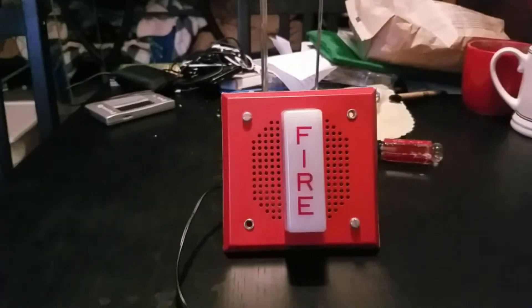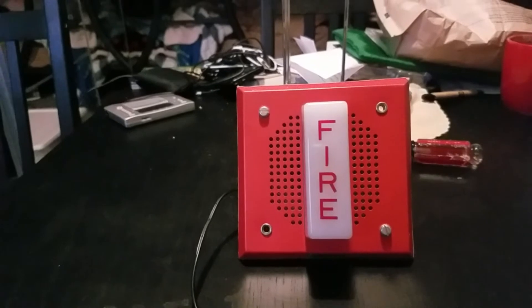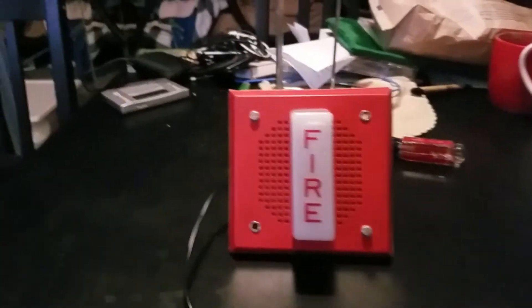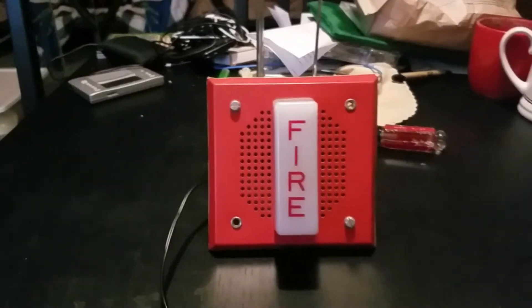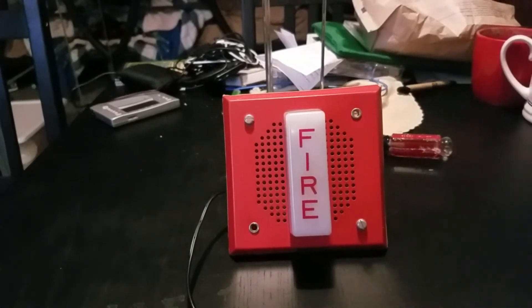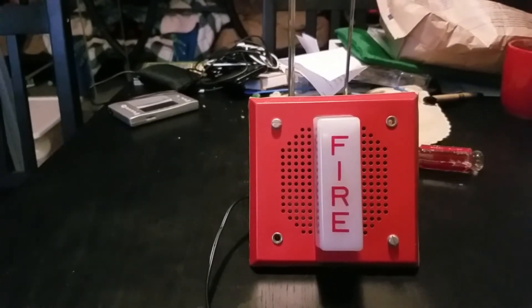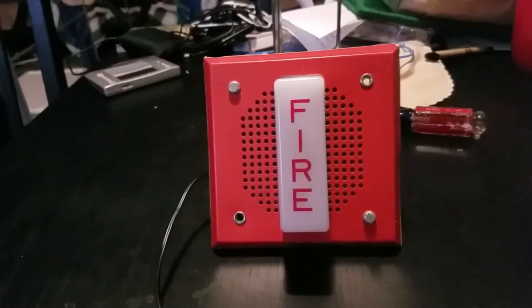Now we're going to test the chime and strobe together. I will give you guys a fair warning with this device — please be very careful with your Wheelock CH70s because I've heard that some fire marshals note these Wheelock CH70s can break real easily with the chime modules. So be very careful. This thing is pretty old. Another weird thing about this device — it does that long polarization for 15 to 20 seconds. I think it has something to do with the components on the circuit board being worn out, because this device is about almost 30 years old.